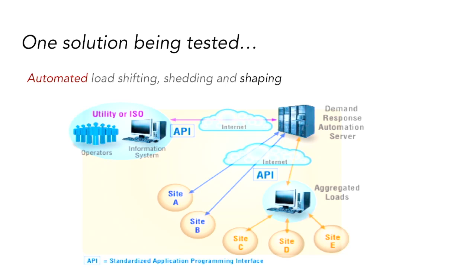The utility or independent system operator publishes price or reliability information from the electricity grid. These are published on the internet in a machine-readable format, so any computer can grab this information and bring it to the facility. At the facility - site A, site B - there's a building control system with pre-programmed strategies. This is important because these strategies are pre-programmed by the facility operator, bringing the building into a low power mode - automatically adjusting temperatures by 2 degrees, turning off some lights, and so on. But it's designed and programmed by the building operator, so no utility does anything to the building.